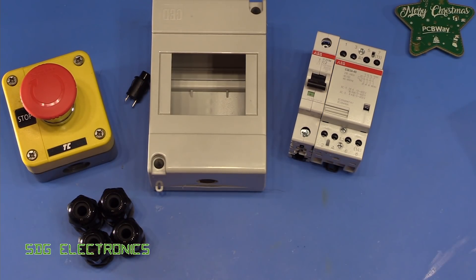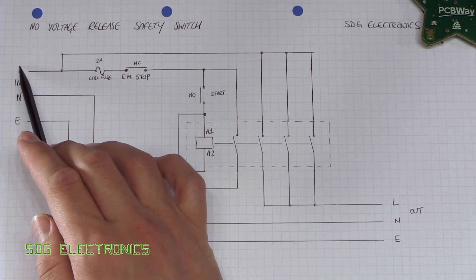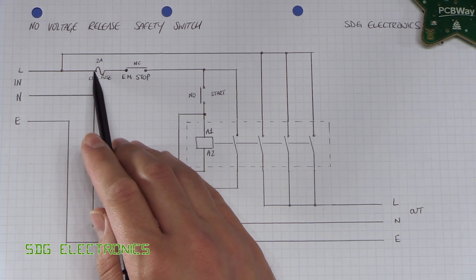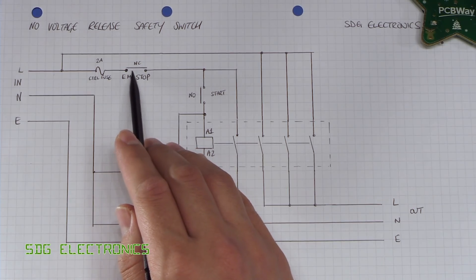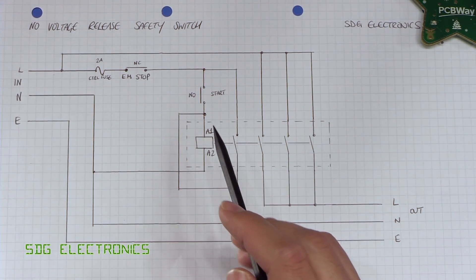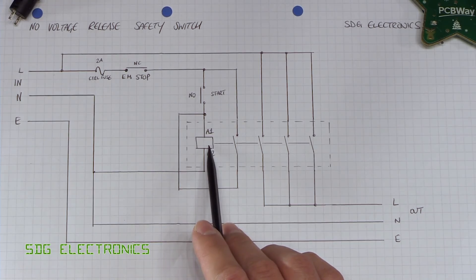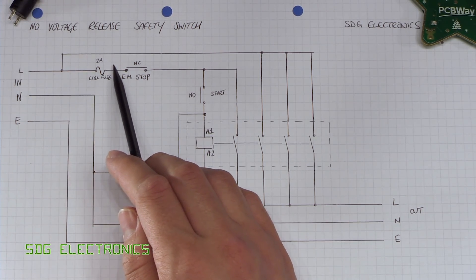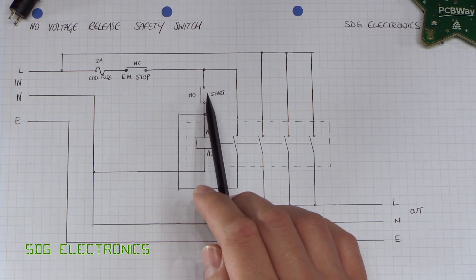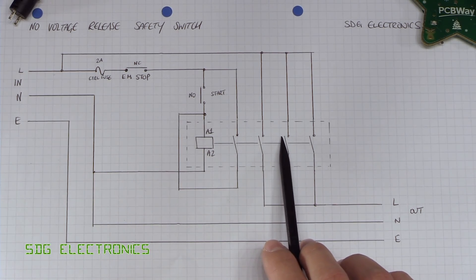Let me explain the circuit. On the left hand side is our mains power in — 230 volts in — and on the bottom right is our 230 volts out to our sockets. We have our two amp circuit fuse, which then goes to our normally closed emergency stop button. When it's in its released position, the contacts we need are the ones that are closed. Then we've got the start button, which is a normally open push button, and that connects our coil. Power goes through the fuse, through the emergency stop button, then stops at the start button. Only when you press the start button does current flow through the coil, energizing it and switching the normally open contacts in.